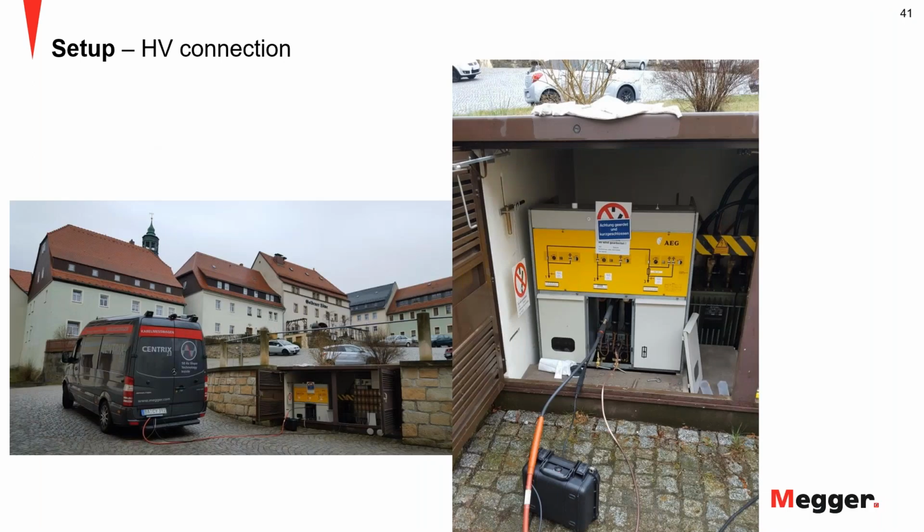Or here, now here you would say, wait a minute, where's the PD coupler here? Here we see a variation of PD system that is increasingly popular with people. They say, you know what, we know all of these splice faults, these assembly faults, they are in the hundreds and thousands of picocoulomb.